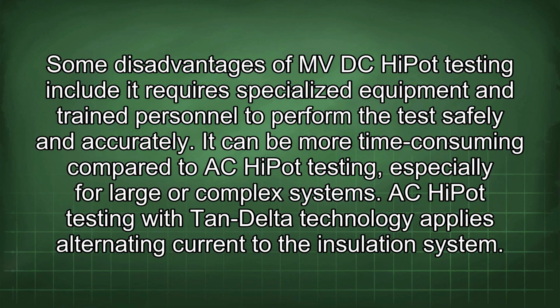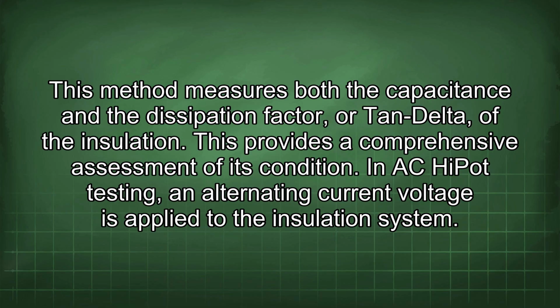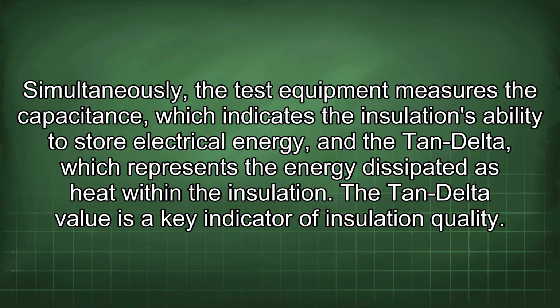AC HiPot testing with tan delta technology applies alternating current to the insulation system. This method measures both the capacitance and the dissipation factor, or tan delta, of the insulation. This provides a comprehensive assessment of its condition. In AC HiPot testing, an alternating current voltage is applied to the insulation system. Simultaneously, the test equipment measures the capacitance, which indicates the insulation's ability to store electrical energy, and the tan delta, which represents the energy dissipated as heat within the insulation.